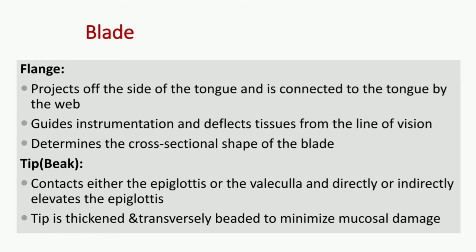The flange of the blade projects off the side of the tongue and is connected to the tongue by the web. It guides instrumentation and deflects tissues from the line of vision, and also determines the cross-sectional shape of the blade. The tip of the blade contacts either the epiglottis or the vallecula, and directly or indirectly elevates the epiglottis. The tip is thickened and transversely beaded to minimize mucosal damage.